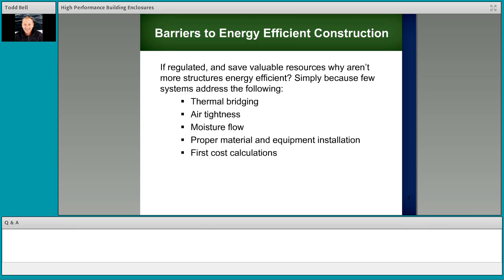Here in Washington State, where I'm at and where we manufacture the SIPs, we have a requirement for blower door testing that has been instituted, I think, since 2007, if I remember correctly, and it's been increasing every year. We went from 5.7 air exchanges at 50 pascals down to 5 air exchanges at 50 pascals, and we're increasing every 3 years as the Washington State Energy Code allows. We're all working towards that 2030 code, but air tightness is really, in my opinion, the biggest part of it.